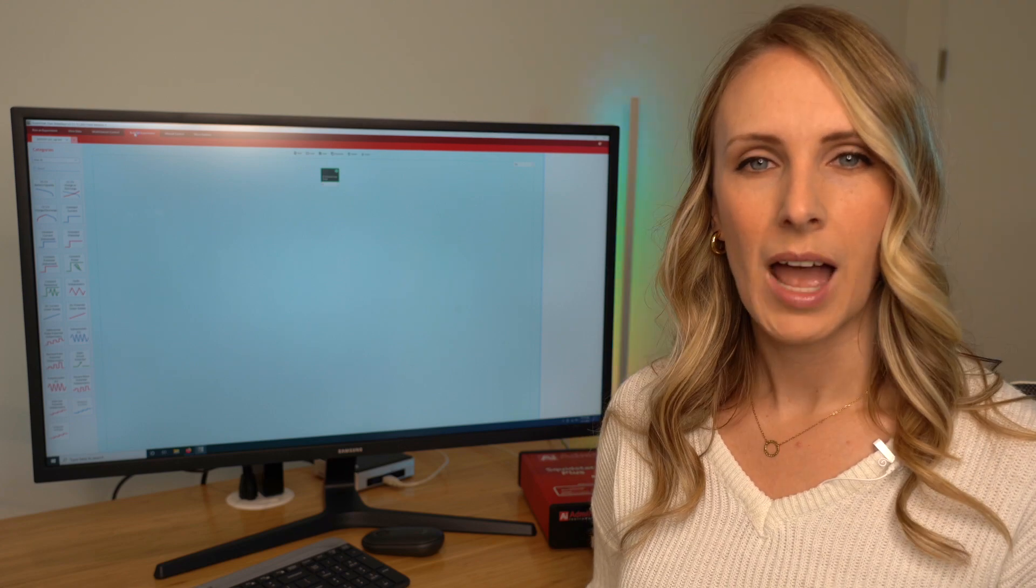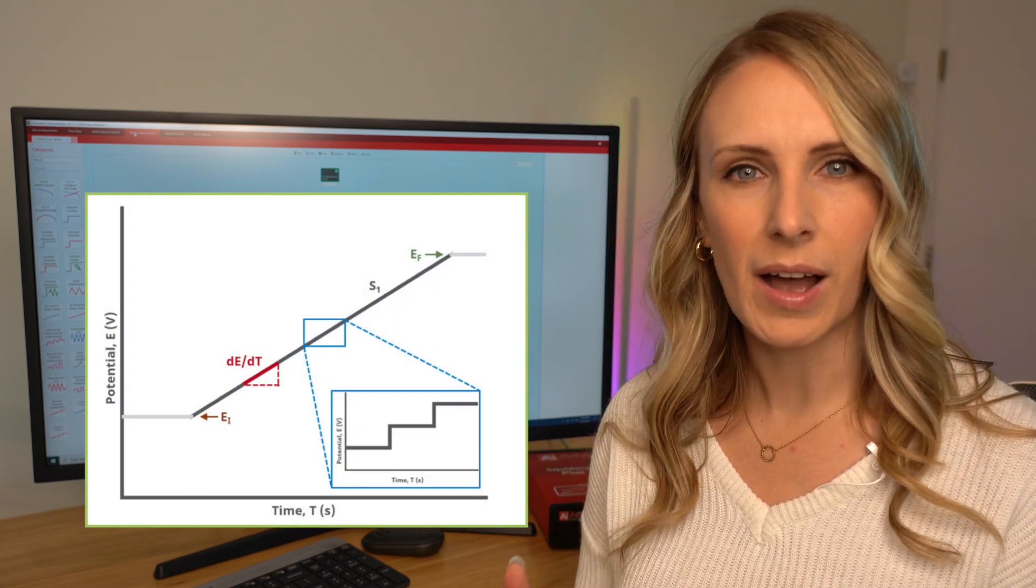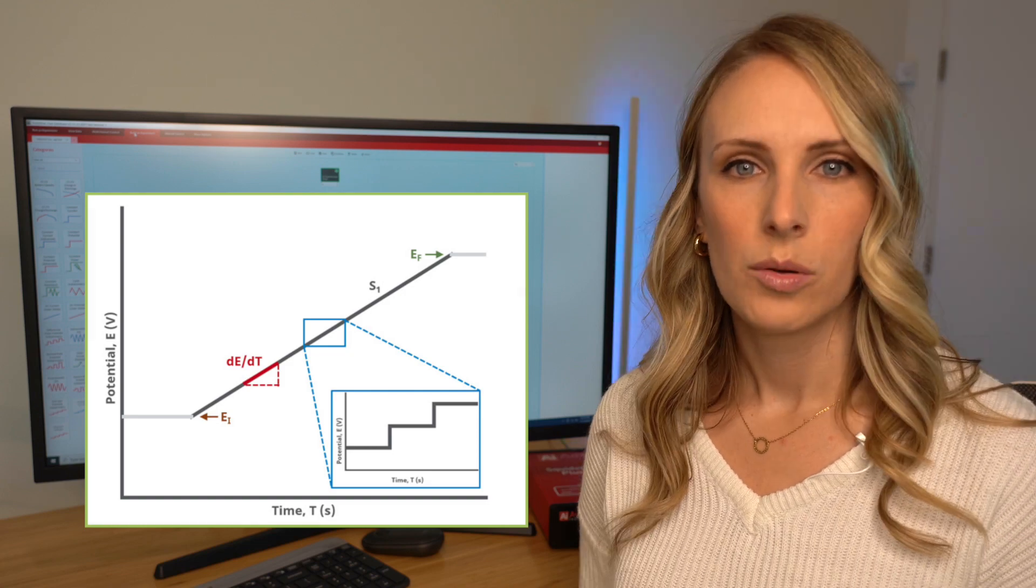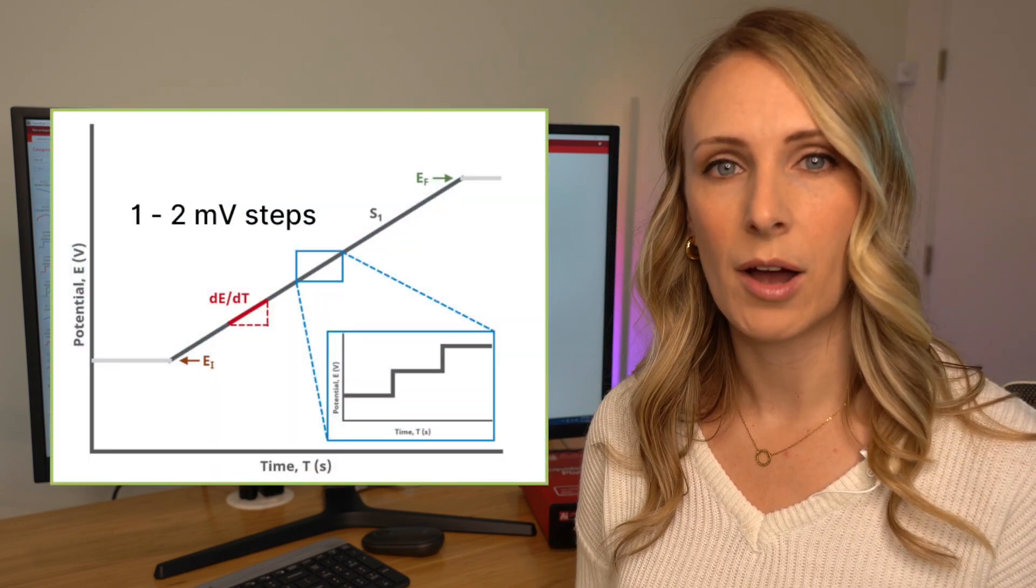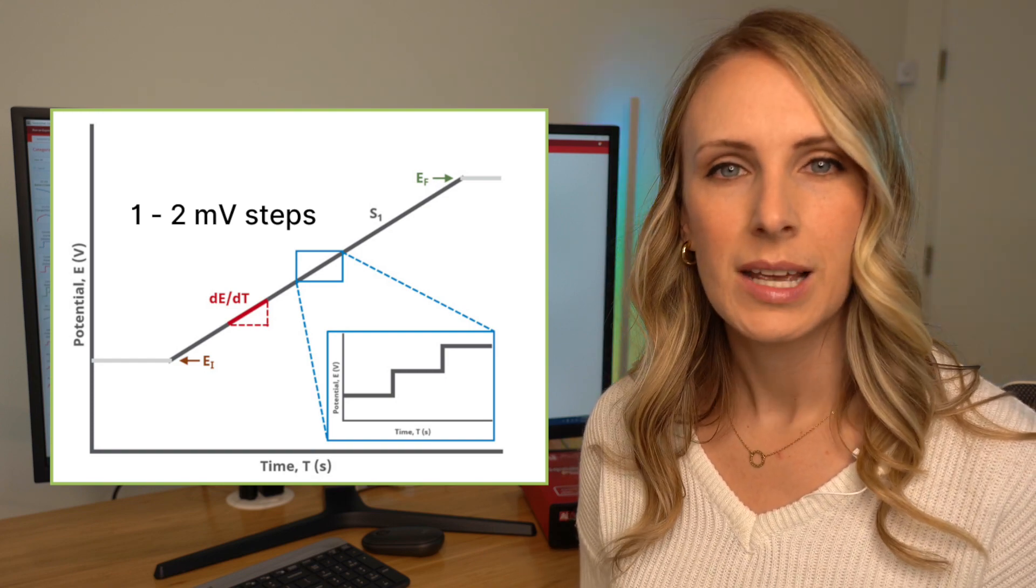Like I said earlier, the input signal for an LSV and CV experiment consists of a linear ramp. However, modern digital potentiostats cannot produce a true linear ramp. They have to approximate the ramp by a series of incremental voltage steps that are defined by the resolution of the analog to digital converter or the ADC. When typical manufacturer's potentiostats are approximating this incremental step for the voltage ramp, they're using a potential of about one to two millivolts. While this works for most experiments, it doesn't work when you want to use a very slow or very fast scan rate.